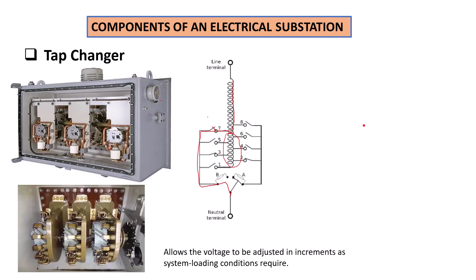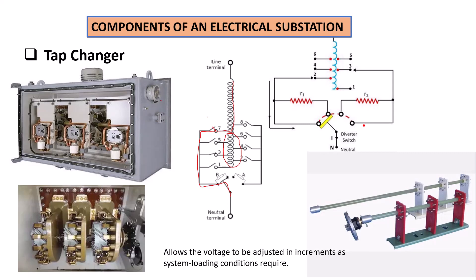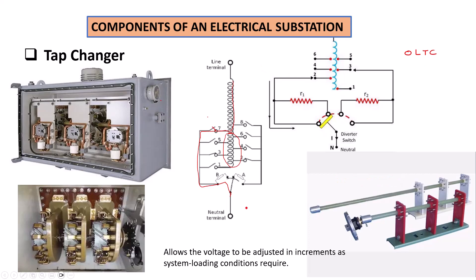Now talking about system loading, we have two types of tap changer. There is the on-load tap changer — meaning the system is still energized — and we also have the off-circuit tap changer, where the circuit is off. The on-load tap changer, or OLTC, is a tap changer where the transformer will remain energized while you are changing the turn ratios. This is very important for applications where voltage conditions fluctuate very frequently, and it is good for power distribution where different types of loads are connected and your transformer remains energized.